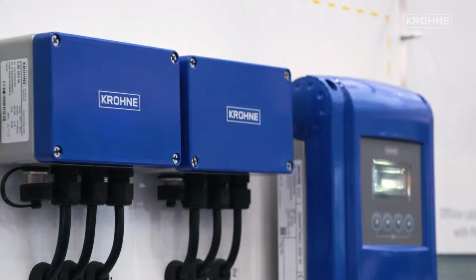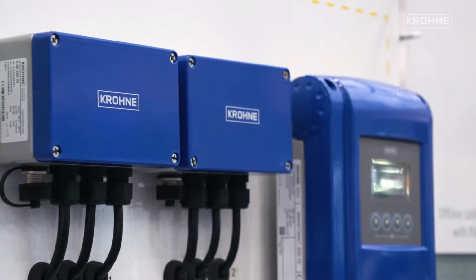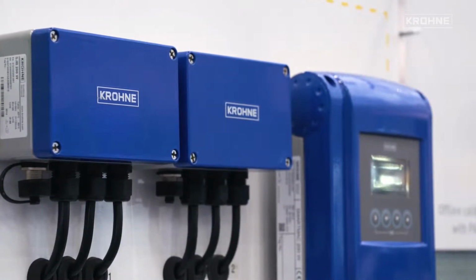So, for example, when he wants to do an online calibration directly in the application, he can use a standard HART handheld. He can connect to the sensor, when it's connected to the PLC system via our junction box, with the HART handheld, and then he has complete access to the sensor.